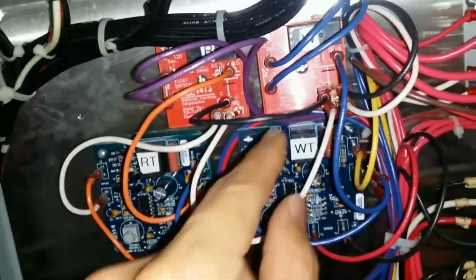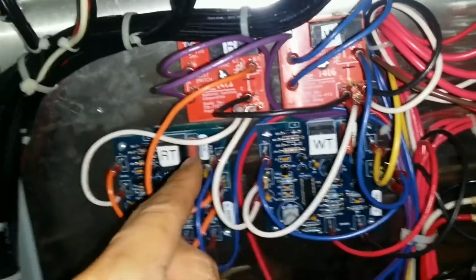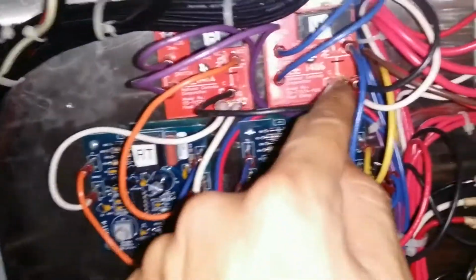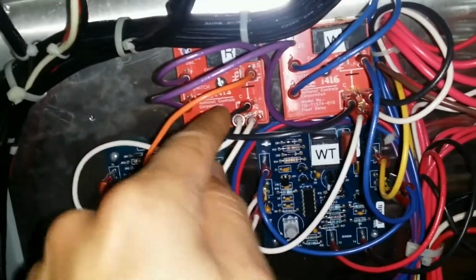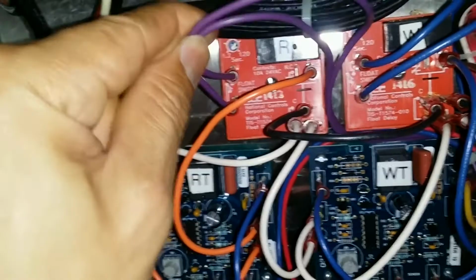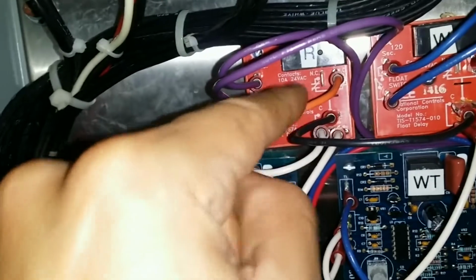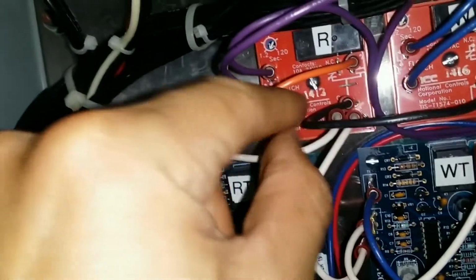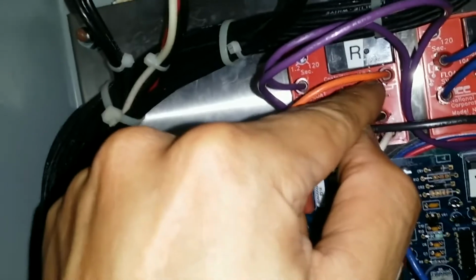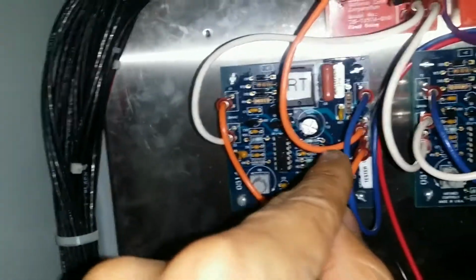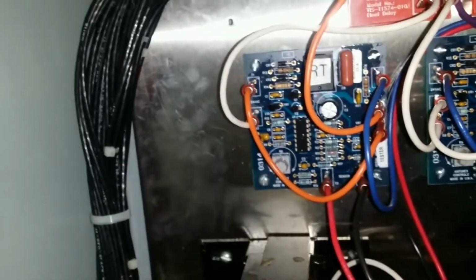If you see, white and black are powered; they are common. So we always got common potential to all of the cards and the SSRs, as you see. Black always comes in and powers these orange floaty SSRs. Let's talk about this one over here, the rinse. Whenever the floaty that is connected to this one shorts, then this SSR will short this contact over here, and it will put black potential into the orange cable. Now the orange cable will energize the circuit card.